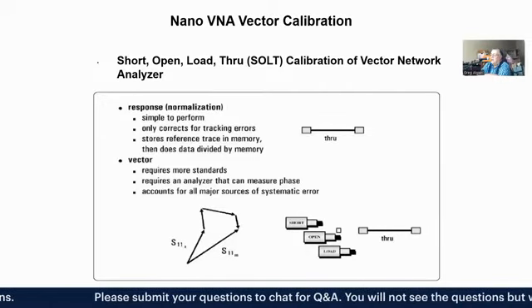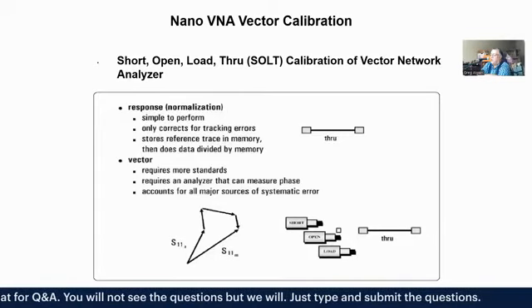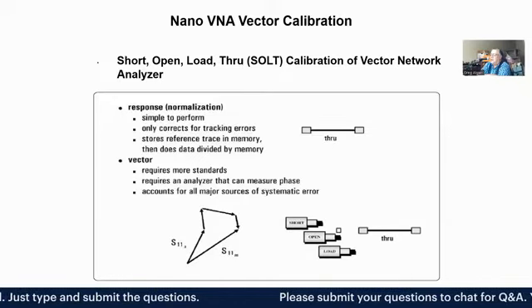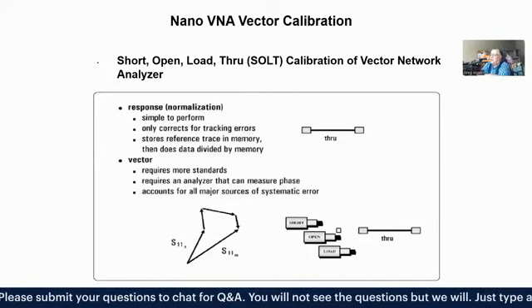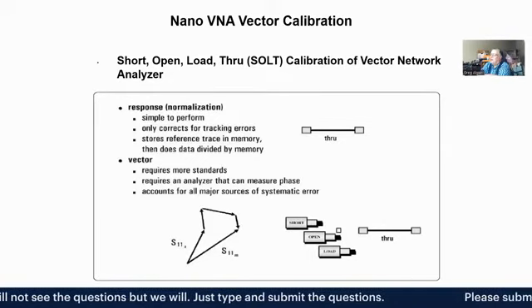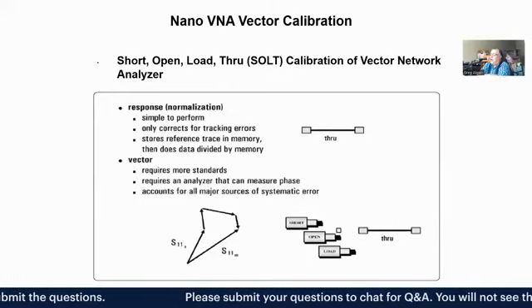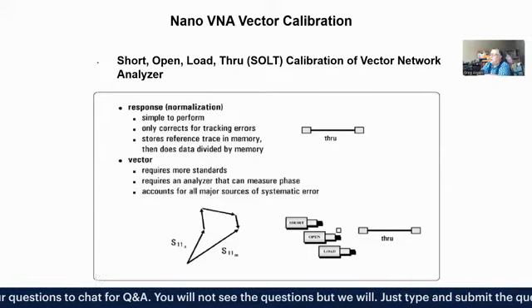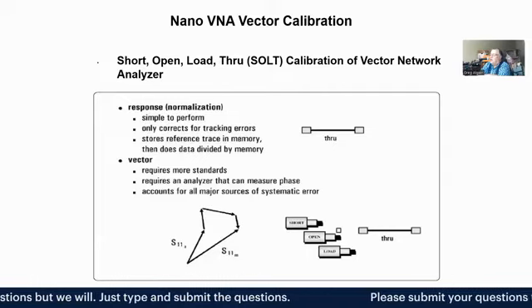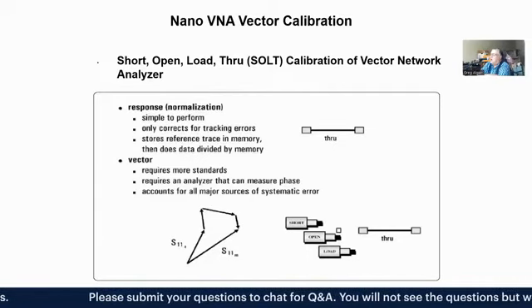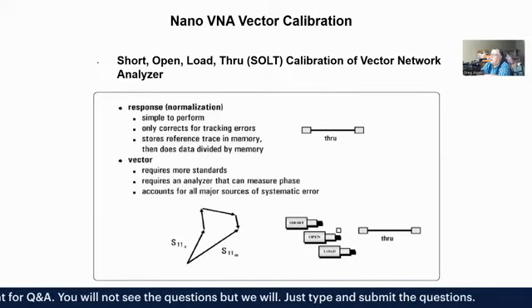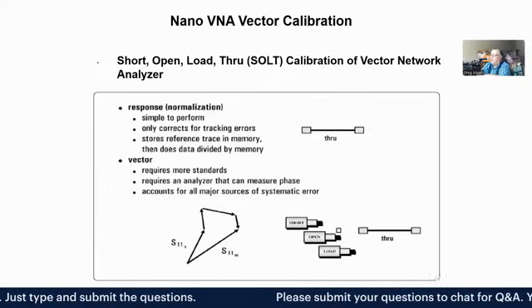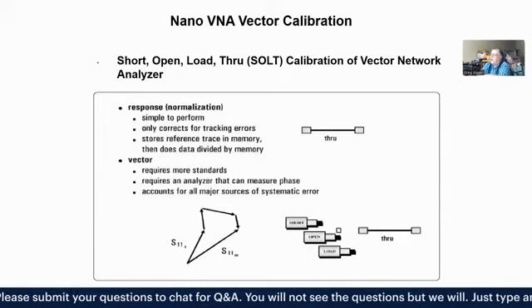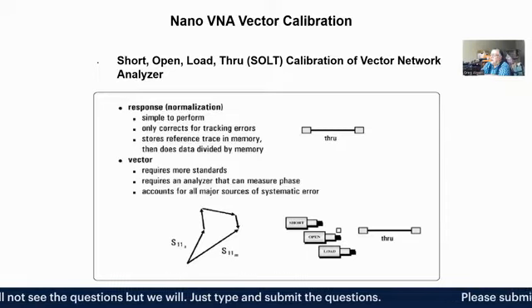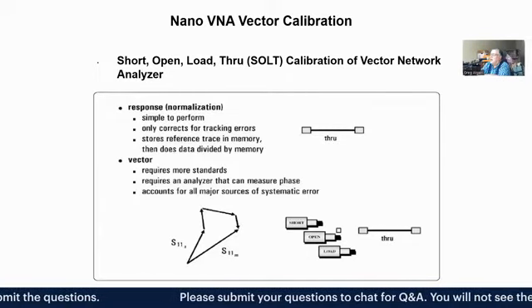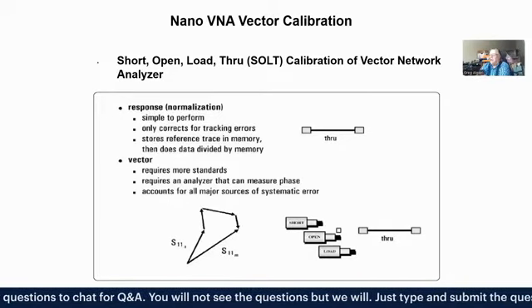And so what happens is, it knows exactly what a short circuit is when you put it on there. We know exactly what a short circuit is from an RF point of view. But when it does the actual measurement, it notices that there are some errors. It's not measuring what an ideal short should be. So what the calibration software does is it figures out what those errors are, and it stores those errors so that when you actually do a measurement, it can use those stored errors, take them out of the measurement so that the measurement you're getting is error-free. It does this with the short, the open, the load, and the through. It stores all of that. And when you then do the measurement, it uses what they call error vectors to take the errors away from your measurement, and you get a very accurate RF measurement.